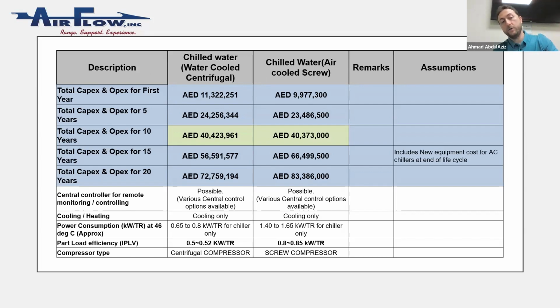If you do this analysis, you'll find after 15 or even 10 years you have almost a break-even point for air-cooled and water-cooled. But after that, you are saving on your chilled water. So as a designer or engineer, you have to look at your application, OPEX, CAPEX, everything to determine whether you should go air-cooled or water-cooled.